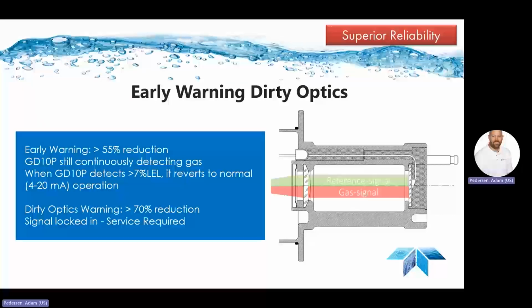There are also two user adjustable levels of dirty optics indications, a warning and an alarm. So the GD10P is so robust that it'll operate and alarm with up to 70% optics signal blockage. Optics can be, again, easily cleaned, and there's no need to declassify the area for service procedures. So when contamination builds to a level where the infrared absorption hits 55% of the calibration value, the device will output 2 milliamps. This is to indicate the device is in an early dirty optics warning state. During this level, the device is still detecting and it's safe to remain online.